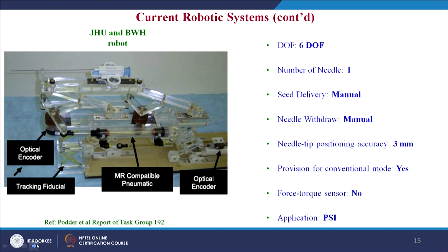The next system was developed in collaboration by the Engineering Research Center at Johns Hopkins University and the Department of Radiology at Brigham and Women's Hospital, Boston. It is a pneumatically operated 6-degrees-of-freedom robotic system for placement of a transperineal prostate needle in a 3T closed-bore MRI. It has one needle, manual seed delivery and withdrawal, needle tip positioning accuracy of 3 mm, provision for conventional mode, and no force-torque sensor. The application is prostate seed implantation.